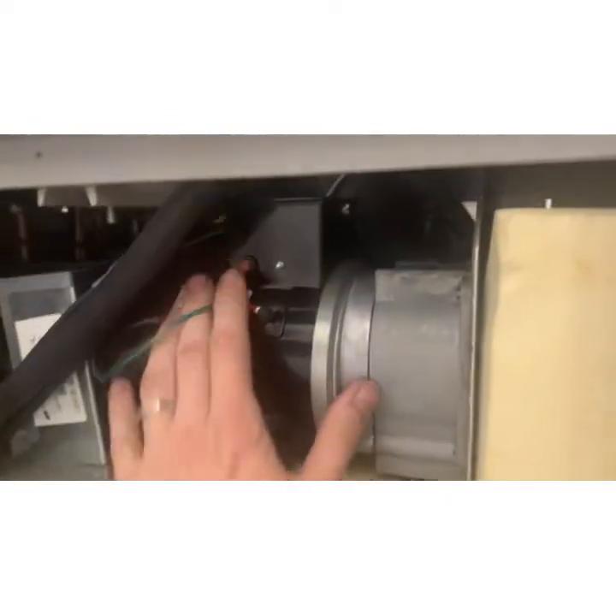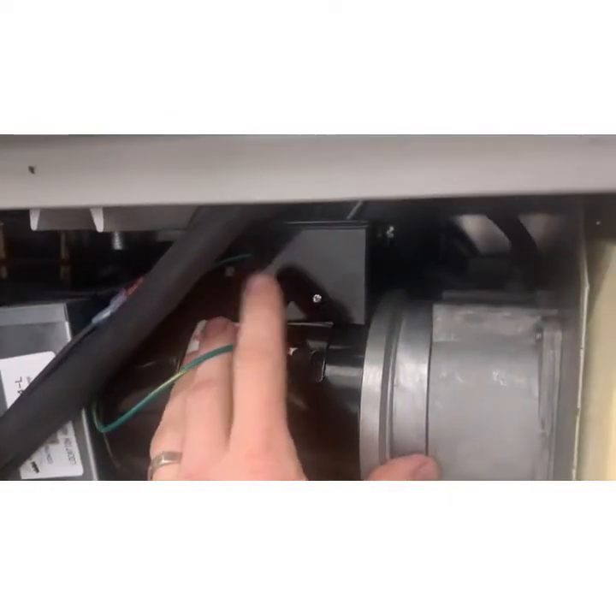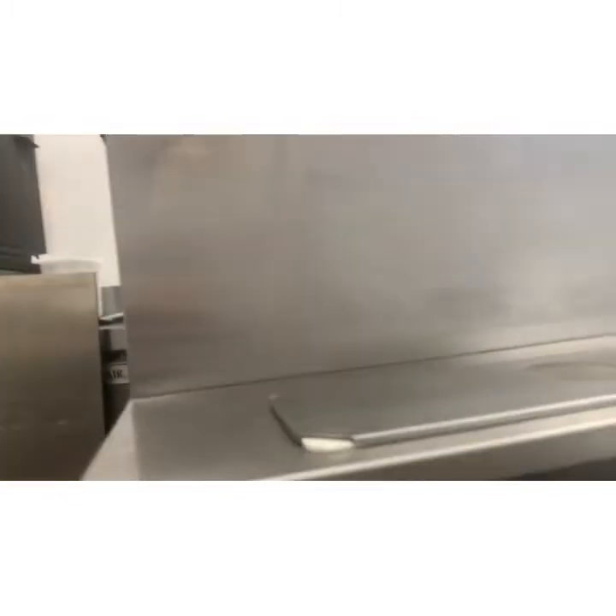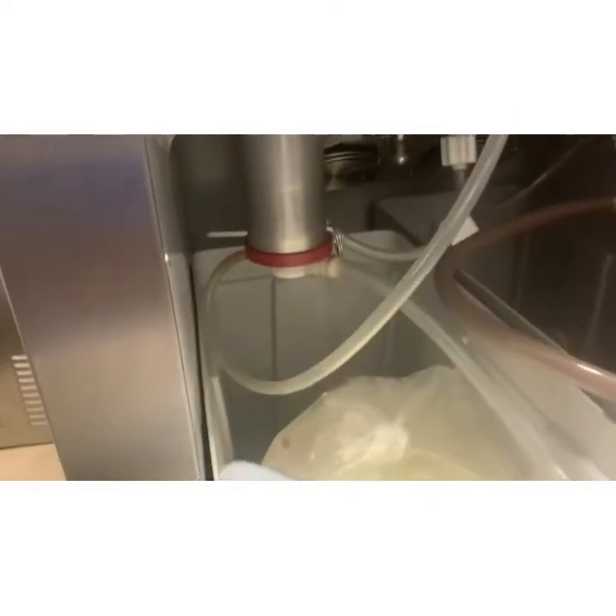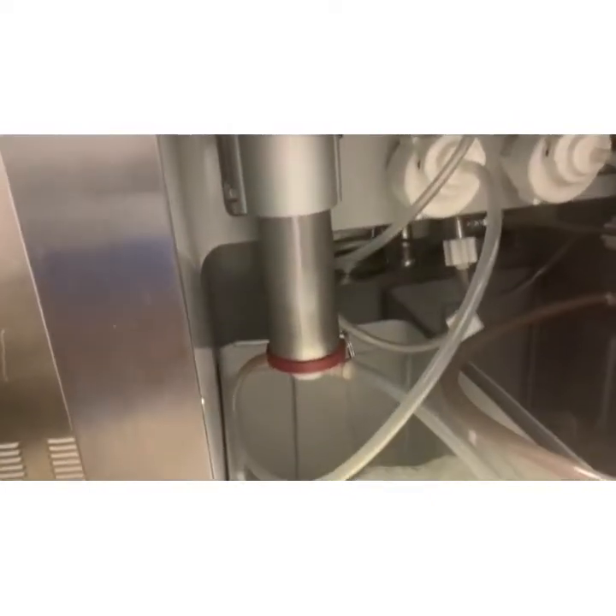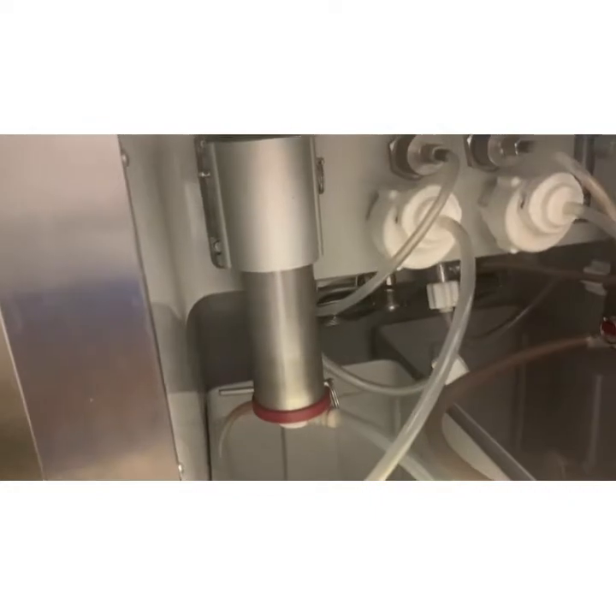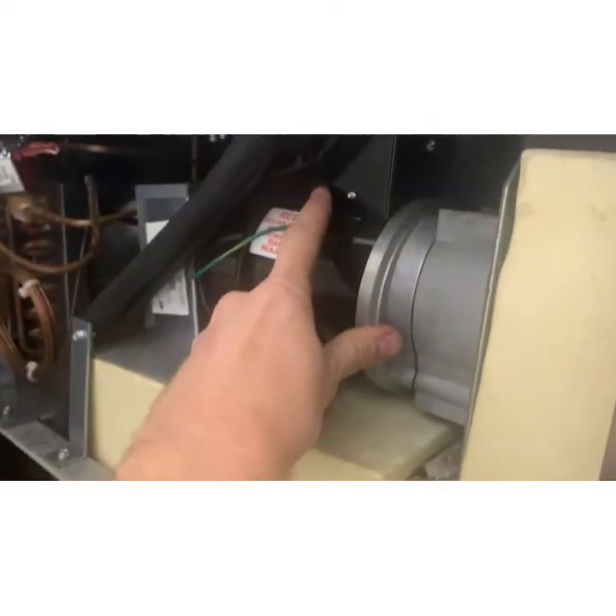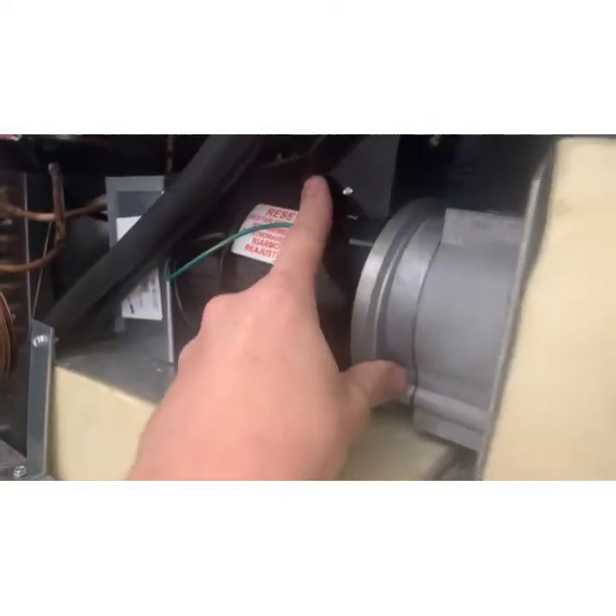I've already opened up the side. There's like a thermal reset I haven't pushed it yet. Oh looky there! So it kicked and stopped. You see that? When I hit pump, I think it tripped the motor again. Okay, so that was reset. If that trips, it's because there's too much load on the motor.